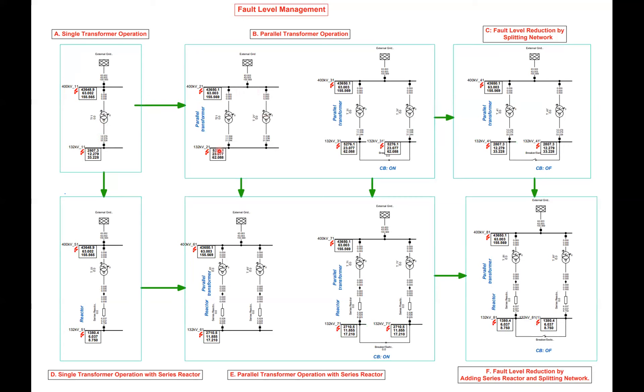In the second case with an identical parallel transformer, the impedance is effectively halved, so the fault current increases to 23 kiloamps. This is because the transformer impedance is halved in parallel. However, when we split the network, the fault current is reduced by half — from 23 down to 12 kiloamps. So the fault level is now reduced from 23 to 12, and technically this becomes identical to the single transformer case.